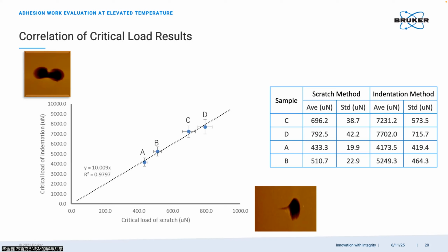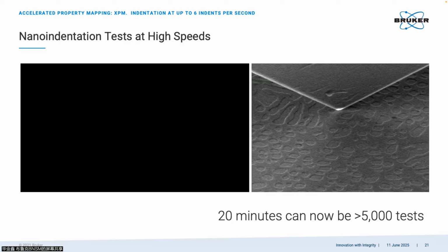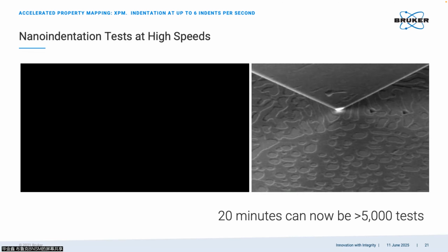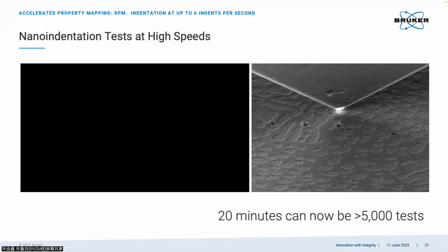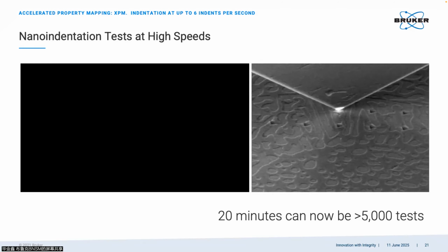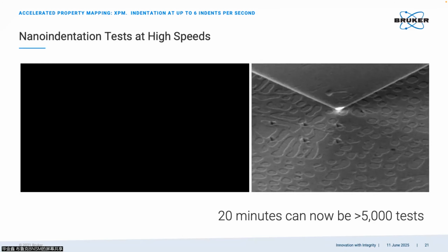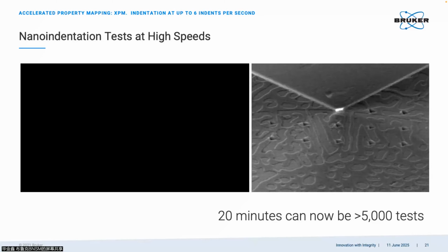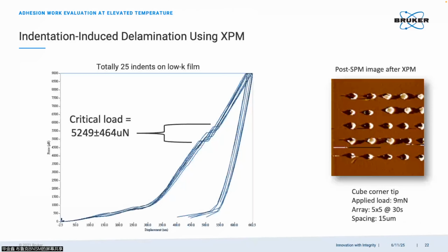So it is an interesting behavior I would like to share with you. It is a proportion correlation for two metrologies or two different probes. And compared to scratch test, indentation test has another two key advantages I would like to share with you. One is that nowadays our instruments are able to perform indentation test in an array at very high speed. So we call it high speed indentation test.